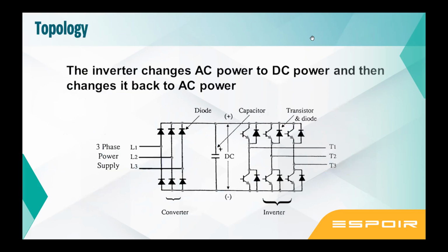Now, let's come to the topology of a drive. We know it primarily does the job of converting the grid frequency to a variable frequency. So how do we convert? It is a black box. We have a rectifier and we have an inverter. We first convert three-phase AC in a bridge rectifier into DC. Then from that DC, we use an IGBT system to convert into variable voltage and variable frequency. So this is the section of an inverter. This is the section of a rectifier.